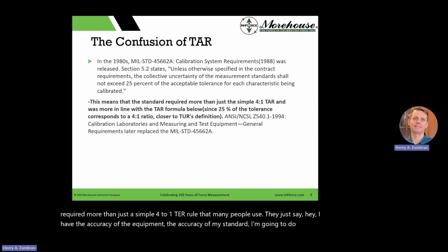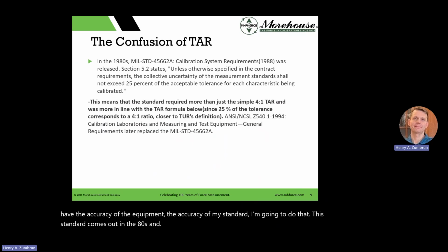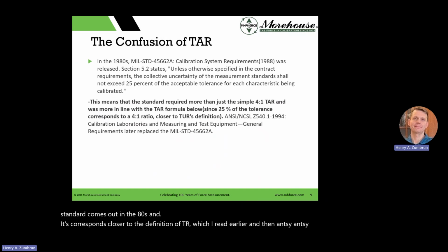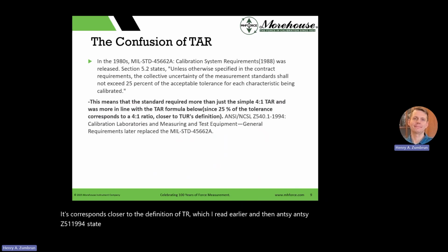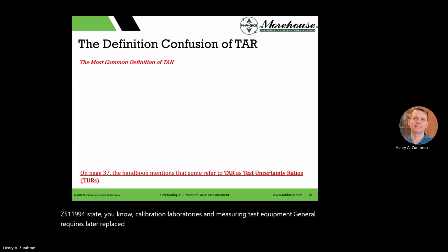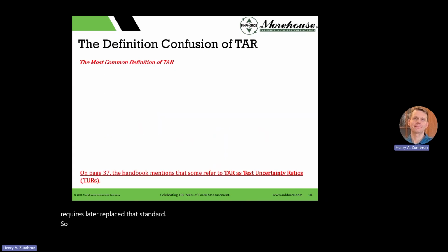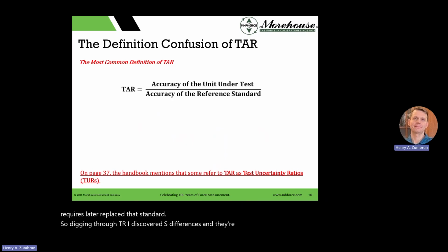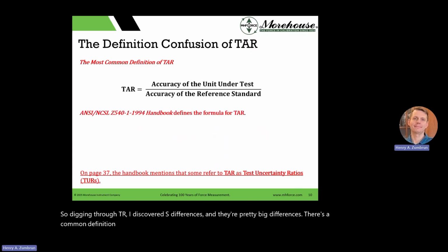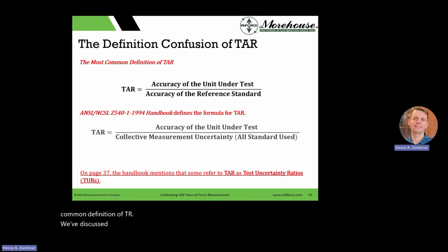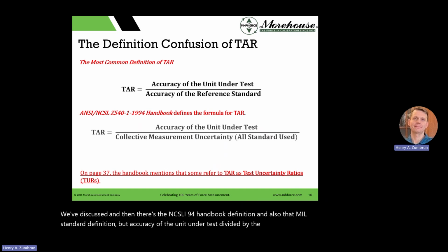This standard comes out in the 80s, and it corresponds closer to the definition of TUR, which I read earlier. And then ANSI NCSL Z540.1, 1994, calibration laboratories and measuring test equipment general requirements, later replaced that standard. So digging through TAR, I discovered differences, and they're pretty big differences. There's a common definition of TAR, which we've discussed. And then there's the NCSLI 94 handbook definition and also that MIL standard definition. But accuracy of the unit under test divided by the collective measurement uncertainty of all standards used.